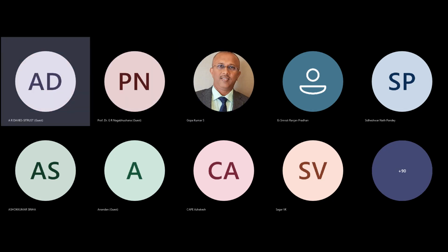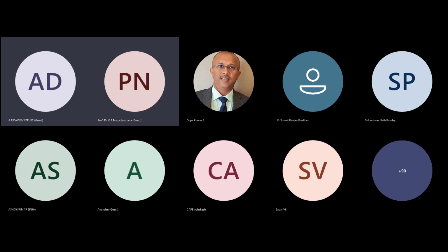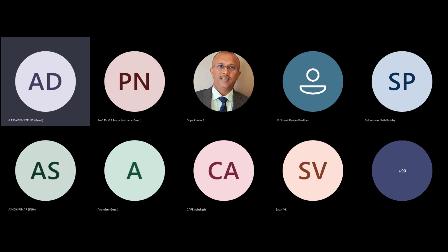And that's the lightning system conductors, earthing, and the grid. Can it be connected to the grid? Because many times in my safety electrical session, this is one of the questions that comes up. I know as per the latest IS 3043, it says to be separated. But if you can throw some light on that, because many engineers attending my session ask, and I also sometimes do not have a proper answer.